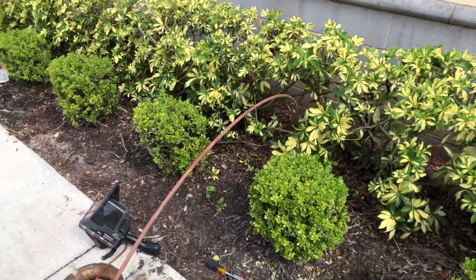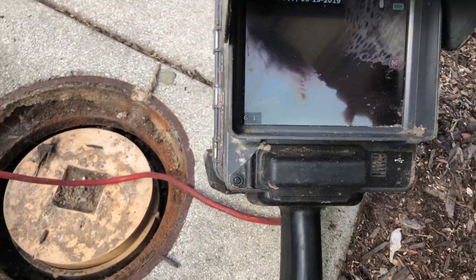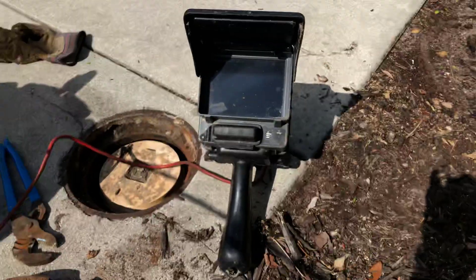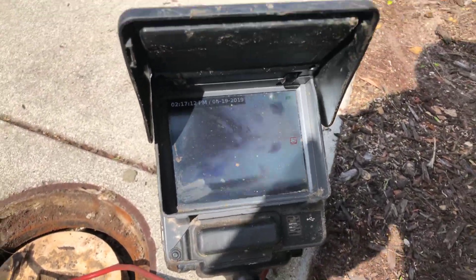Fred Burroughs with plumbers — we're at a commercial cabling job. We've cabled this drain line and opened the drain. We've got water flowing down there, you'll see it flowing by. You can see it on the camera. The bottom of the pipe is actually right here to the side. The issue was a paper blockage about eight feet back. See the water flowing right now.